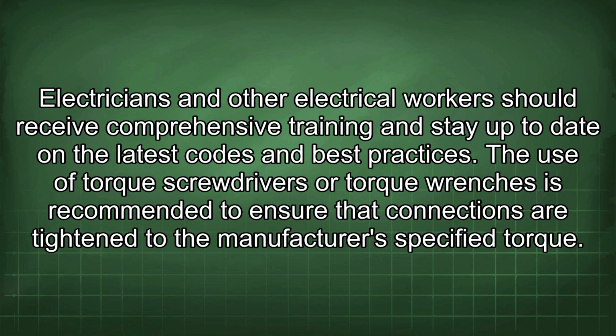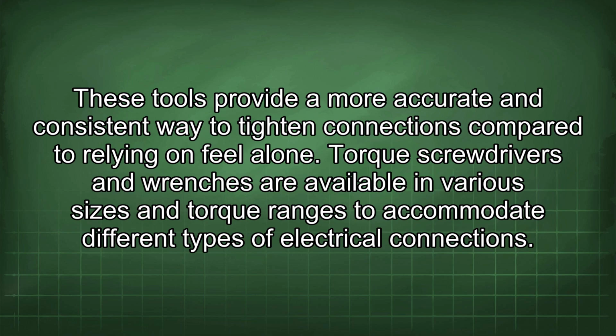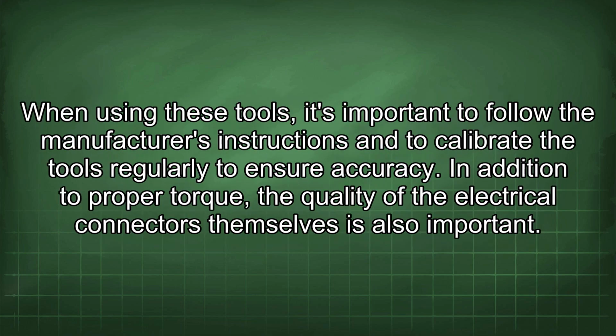The use of torque screwdrivers or torque wrenches is recommended to ensure that connections are tightened to the manufacturer's specified torque. These tools provide a more accurate and consistent way to tighten connections compared to relying on feel alone. Torque screwdrivers and wrenches are available in various sizes and torque ranges to accommodate different types of electrical connections. When using these tools, it's important to follow the manufacturer's instructions and to calibrate the tools regularly to ensure accuracy.